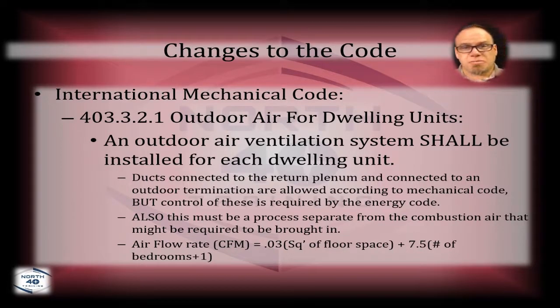So you've got a special system to bring air in from the outside so that it can support the burning process with that appliance. That's it, one system. Okay, and there are sections of code that tell you that has to be a mechanical system and it has to be controlled so that the air that comes in to be burned can be controlled on, off, and whatnot. Not just an open hole to the outside.